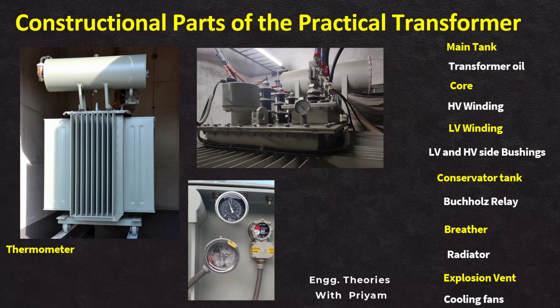The next component that we want to talk about is the oil gauge. The oil gauge in a transformer is typically located on the transformer tank and serves as a critical indicator of the oil level within the unit. Positioned near the conservator or on the tank's exterior, the oil gauge provides real-time information about the quantity of oil present inside the tank. The measurement is essential for ensuring proper cooling, insulation, and overall functionality.